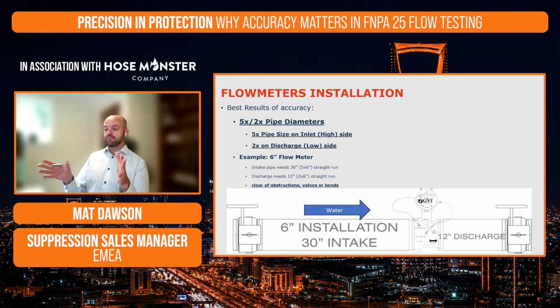And basically what we're looking for there is to get a stable and fully developed flow profile to make sure that the water goes through without turbulence, eliminates excessive swirl and things like that. On the discharge, similar principles apply, but this time we just need a 2x. So again, still a 6-inch installation, obviously, and that means that we need a 12-inch length of pipe for the discharge. And again, we're just looking to eliminate excessive swirl, turbulence, and we're looking for stable, repeatable performance.